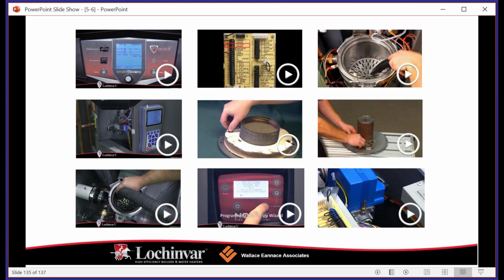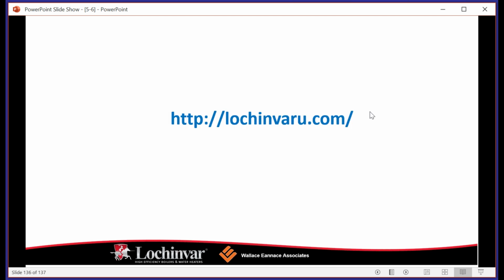So one of the things, and again, this is crucial, is combustion analysis. If you don't have a combustion analyzer on your truck, you need to get one. Like I said, I've been working with condensing boilers for quite some time. I did tech support at Aerco when I first came on there. And there are some things that you cannot resolve without a combustion analyzer if you're working on high efficiency condensing modulating boilers.